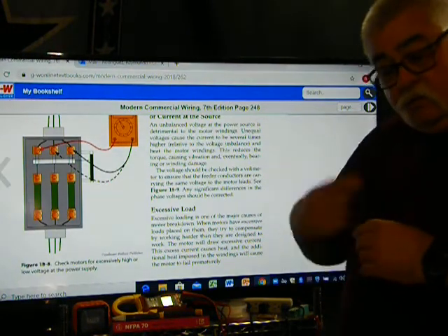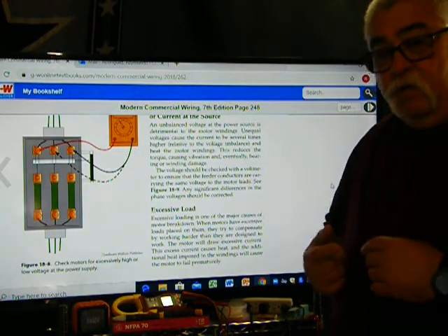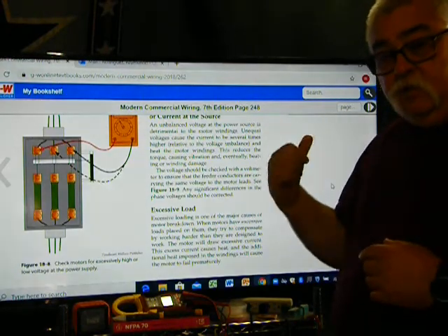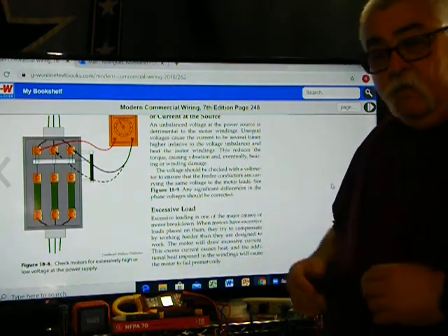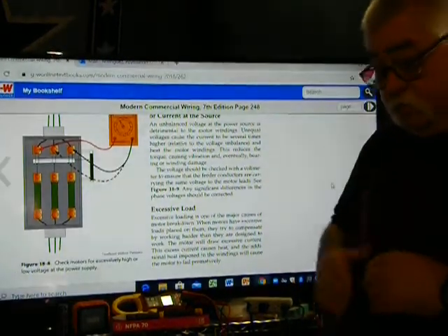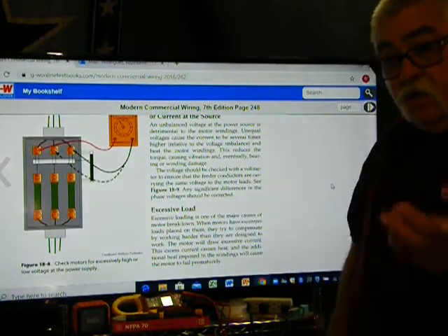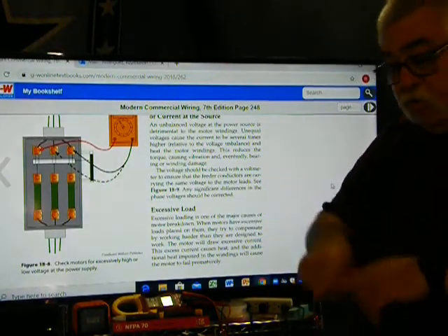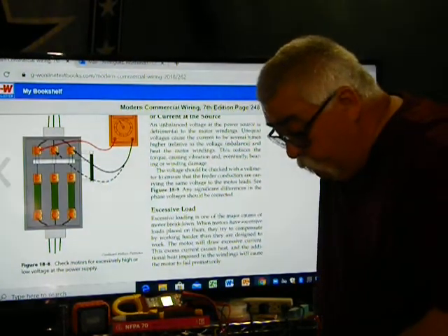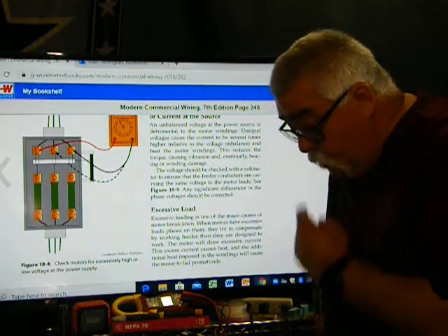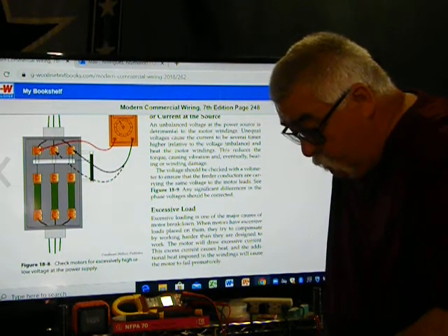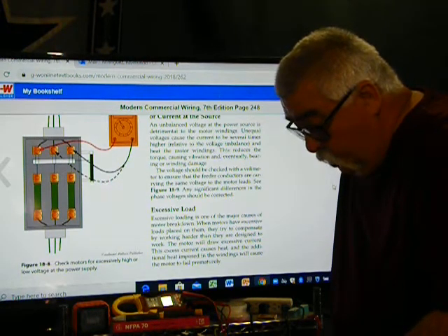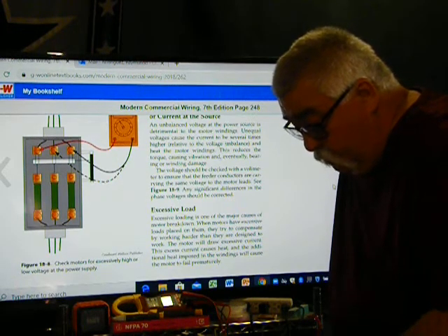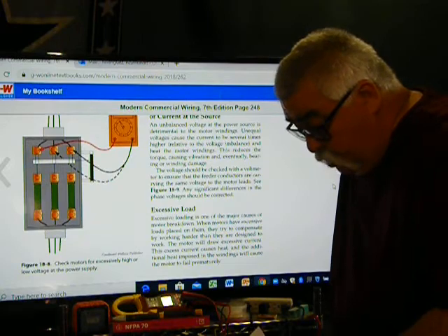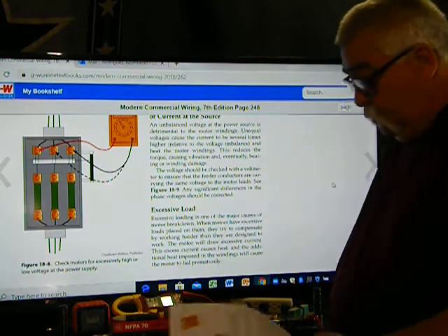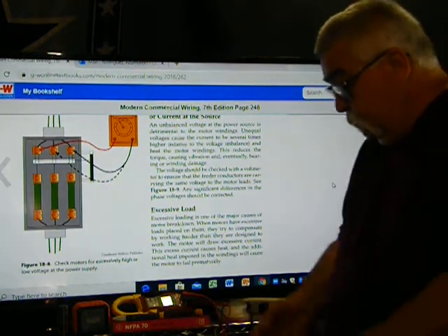If that excessive current stays on there for an extended period of time, it puts heat on the windings, and the windings start to fall apart and can short out between each other. That's what I was talking about, checking your windings, making sure your windings aren't short-circuited. So the current shown on the nameplate is the maximum rated current for the motor. During normal operations, the current drawn should be somewhat less. So you should always have something less.